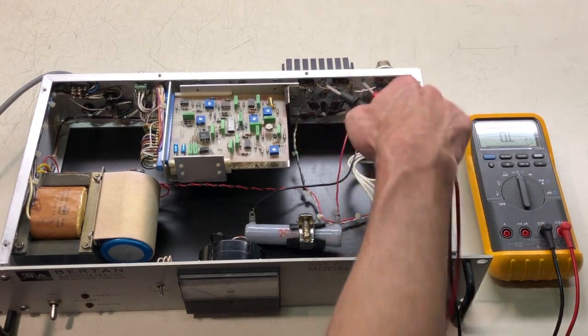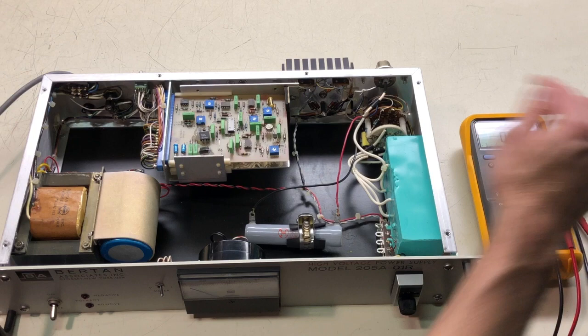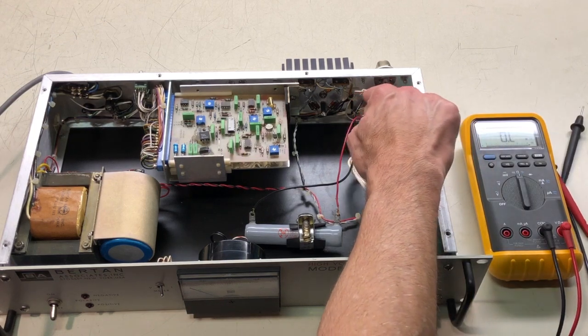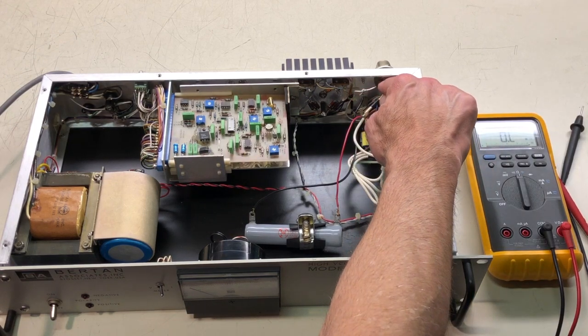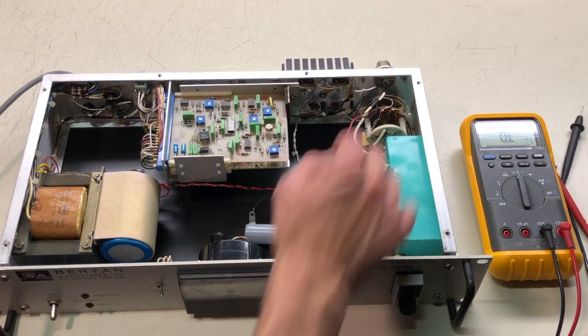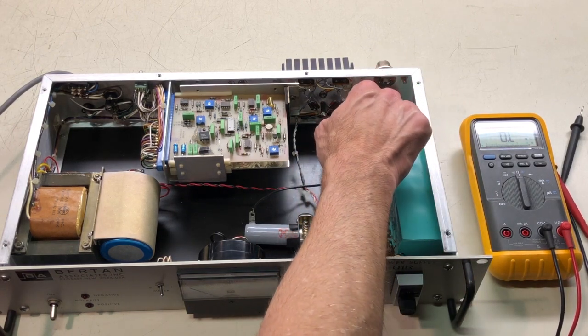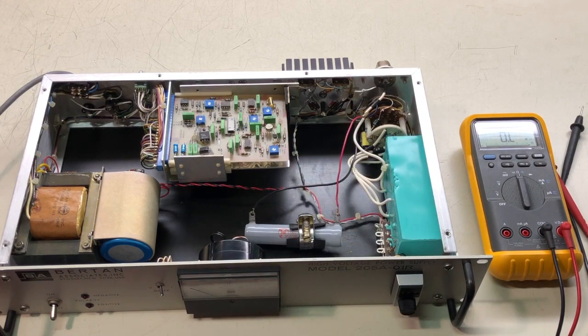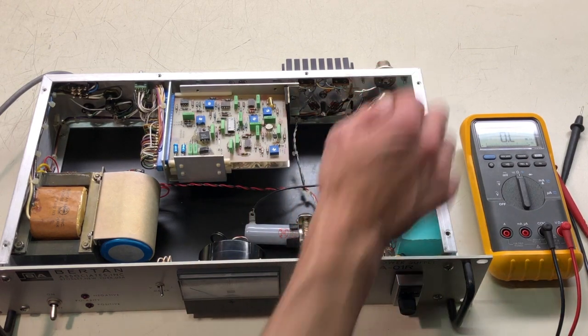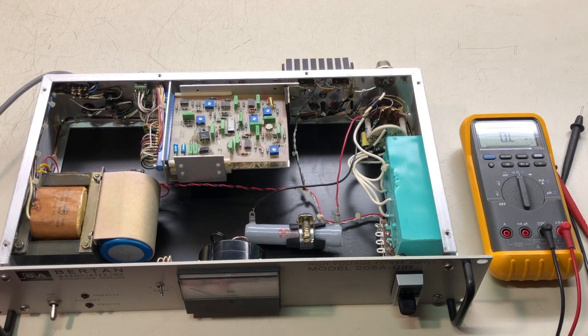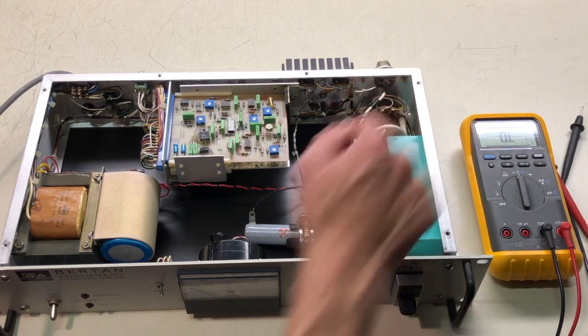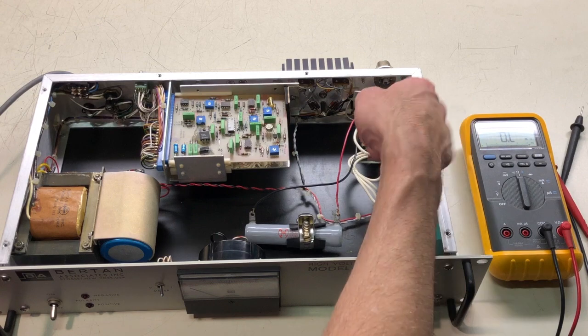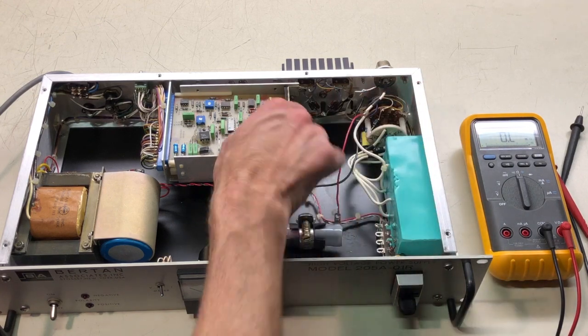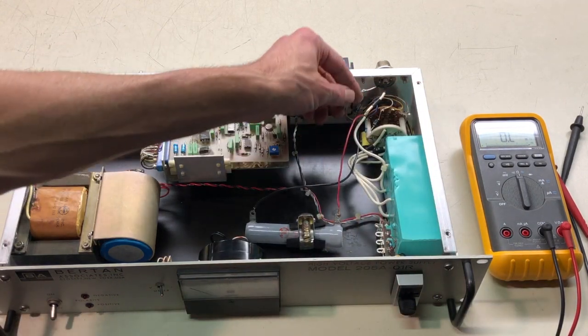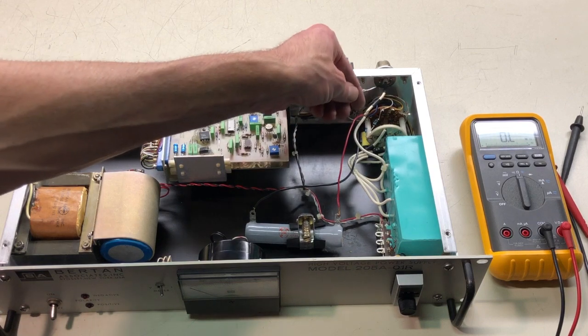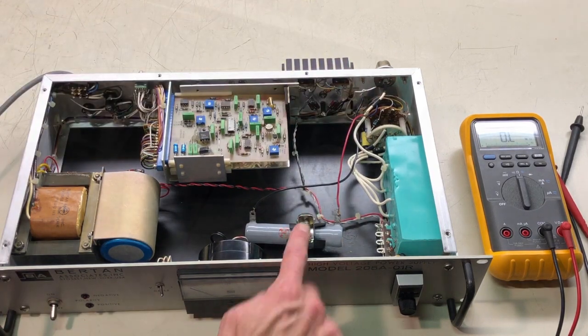I don't know, it looks like it routes around. So if there's enough room on that wire to pull it over, instead of trying to repair this, I'll just move that over to that terminal. But it's already a ground connection, so that doesn't look like a high voltage wire anyways. It's much thinner insulation, so we don't have to worry about anything there with high voltage, but we'll just move that over. But this splice right here, they didn't cut the wire. It looks like they cut the insulation away and then sort of spliced in. So we'll clean that up. We'll get this resistor out of there.